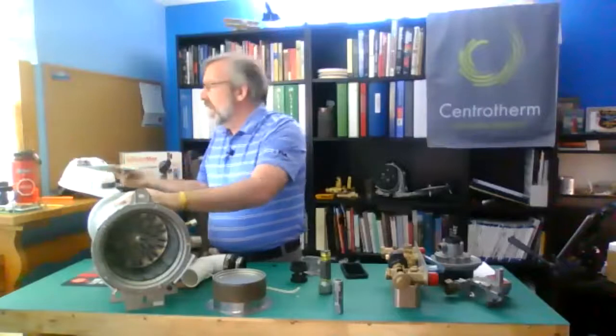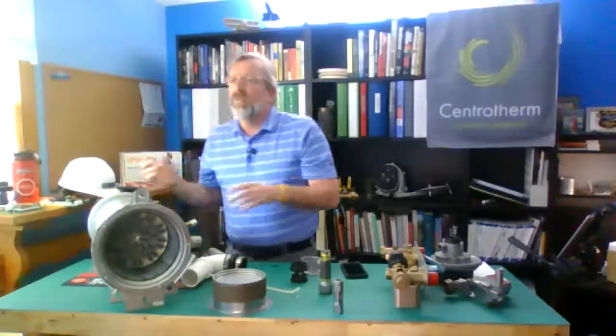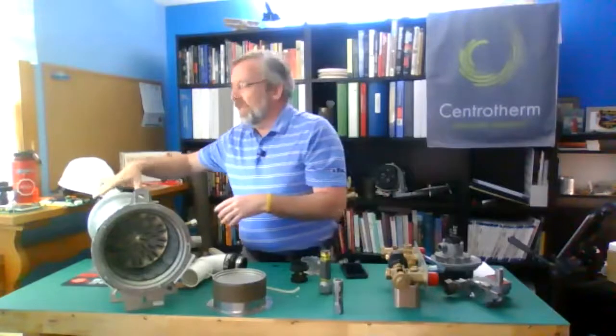You can use a little Poland Spring water bottle, doesn't really matter. If you really want to be efficient, you can use a 5-gallon bucket that you put underneath, take the condensate drain off to collect it, and then you're going to pour down through the top, clean everything out down through. So it's pretty simple. That's what's really involved in it.